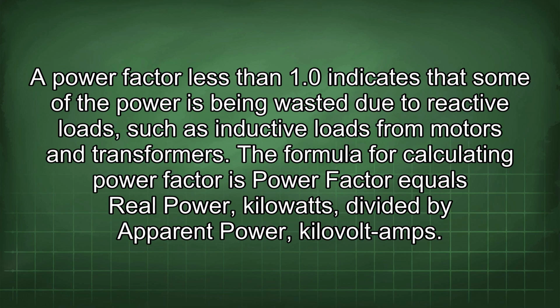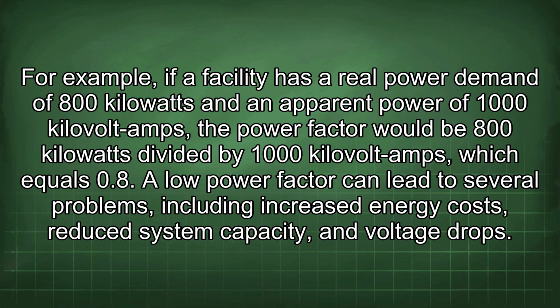The formula for calculating power factor is power factor equals real power, kilowatts, divided by apparent power, kilovolt amps. For example, if a facility has a real power demand of 800 kilowatts and an apparent power of 1000 kilovolt amps, the power factor would be 800 kilowatts divided by 1000 kilovolt amps, which equals 0.8. A low power factor can lead to several problems, including increased energy costs, reduced system capacity, and voltage drops.